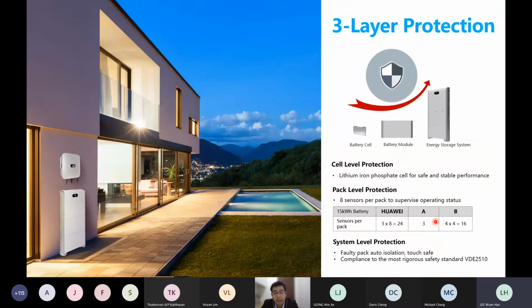Yeah, it can go up to 480 degrees Celsius operation. At the same time, it doesn't produce oxygen during its operation. So we know that fire feeds on oxygen, so that's one of the ways to mitigate the fire issue. And then for the pack level, the battery module level, we have 8 sensors per pack to monitor the cell temperature. So if anything goes wrong, the battery module will then be turned off.